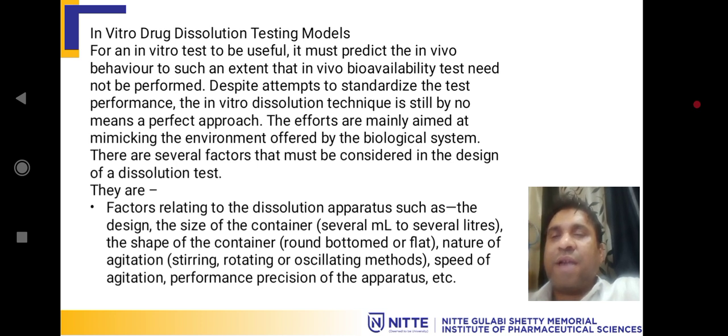There are several factors that must be considered in the design of a dissolution test. Factors are the dissolution apparatus, such as design, size of the container, how many ml or liters, shape of the container, round bottomed or flat, nature of agitation, stirring, rotating, oscillating, speed of agitation, performance precision of the apparatus, etc.